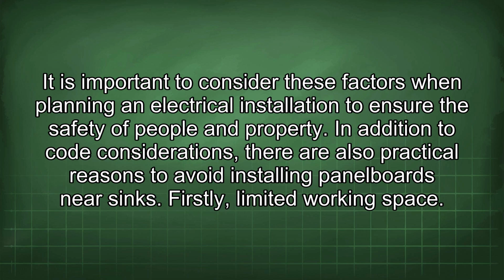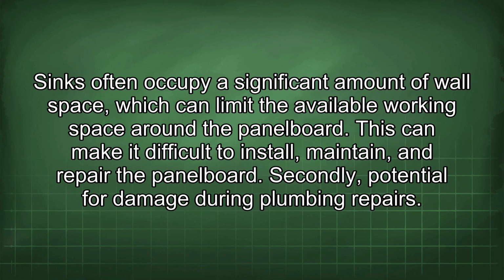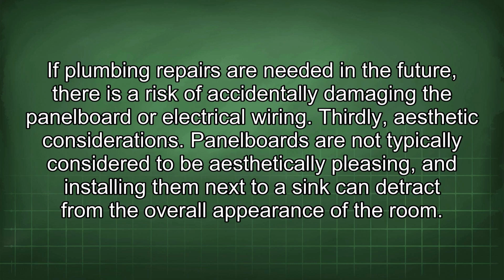In addition to code considerations, there are also practical reasons to avoid installing panel boards near sinks. Firstly, limited working space. Sinks often occupy a significant amount of wall space, which can limit the available working space around a panel board. This can make it difficult to install, maintain, and repair the panel board. Secondly, potential for damage during plumbing repairs. If plumbing repairs are needed in the future, there is a risk of accidentally damaging the panel board or electrical wiring. Thirdly, aesthetic considerations. Panel boards are not typically considered to be aesthetically pleasing, and installing them next to a sink can detract from the overall appearance of the room.